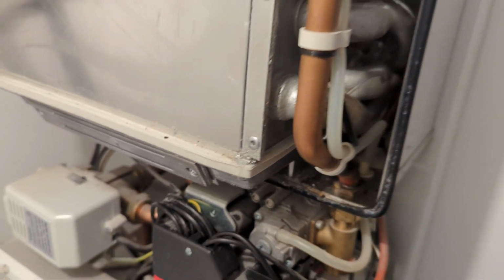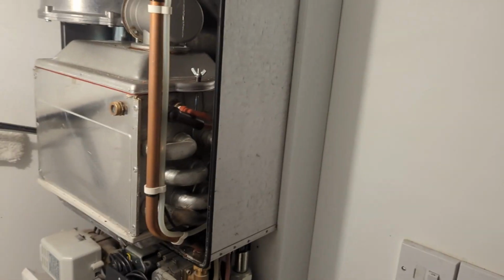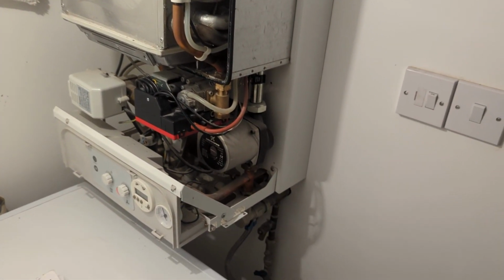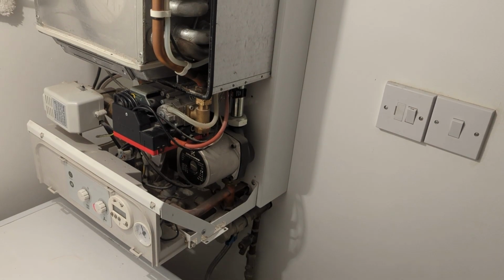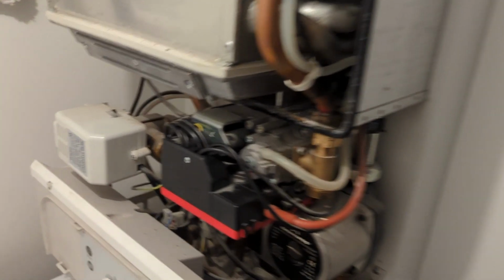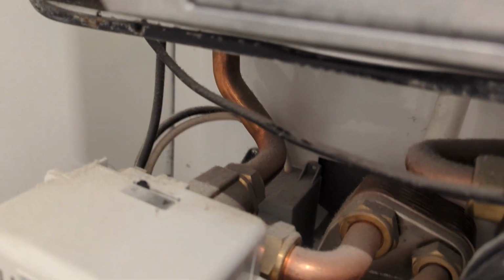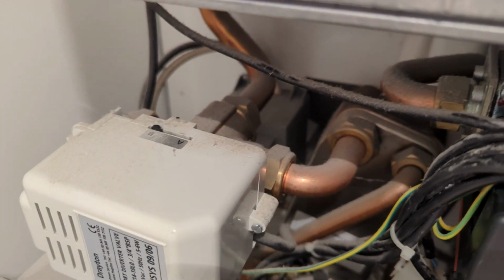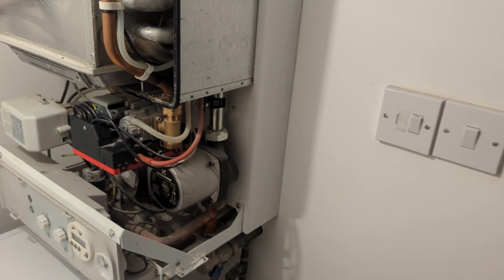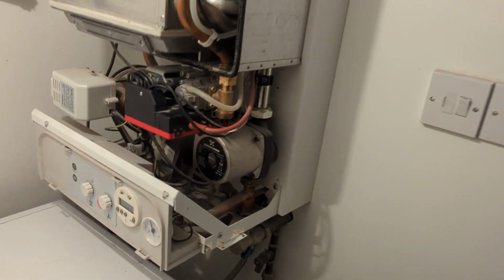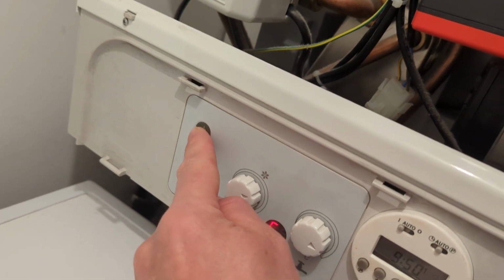There I'm putting it into service mode, and strangely enough, when I put it into service mode, the boiler fires up. The diverter valve changes over to heating there, which is A. No, sorry, B. That's heating. Fan kicks in, the pump kicks in, and it ignites. So that tells me the boiler is actually working. So what is the problem?